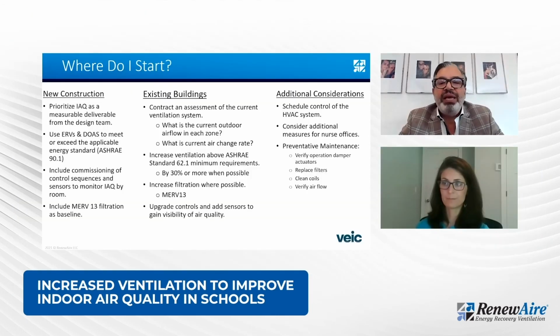Of course, making sure that you look at preventative maintenance becomes very critical, because the second you have a fully loaded MERV 13 filter, you may potentially end up seeing a collapse of that filter, and now you're bypassing that air. So cleaning coils, making sure you've got the airflow, all of that preventative maintenance or just general maintenance becomes paramount in ensuring proper indoor air quality.